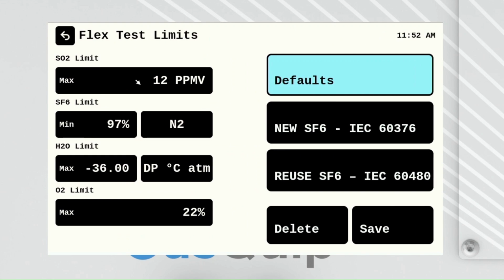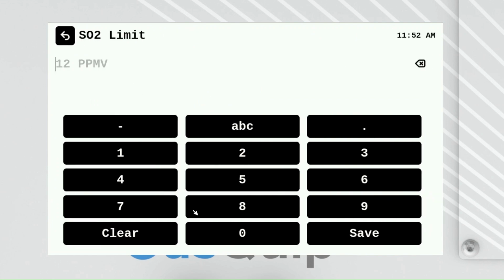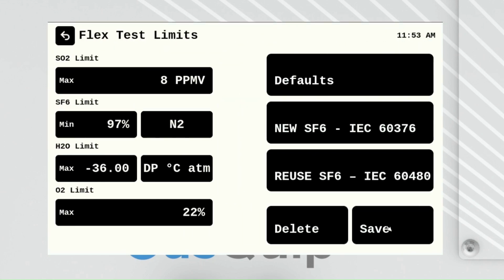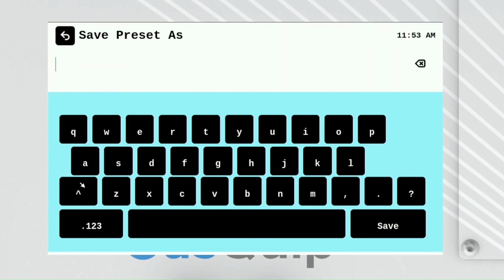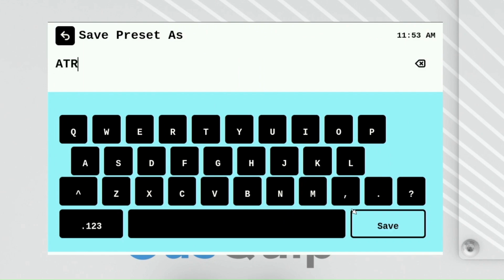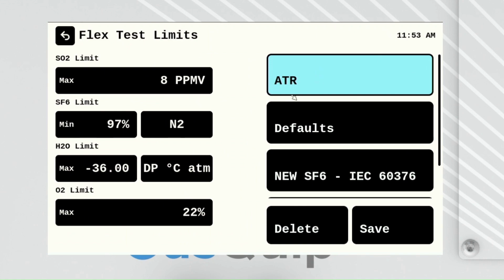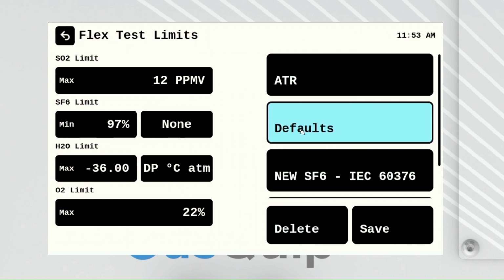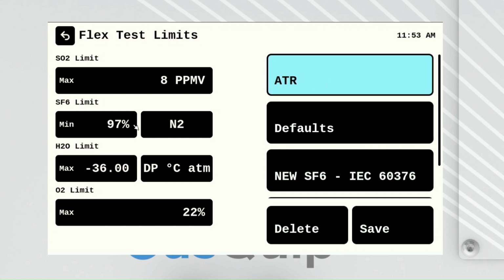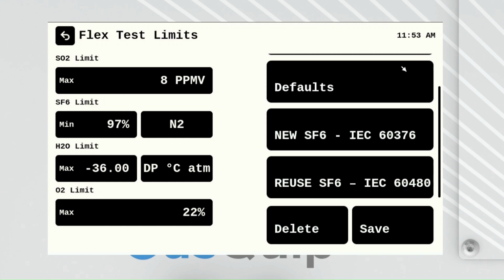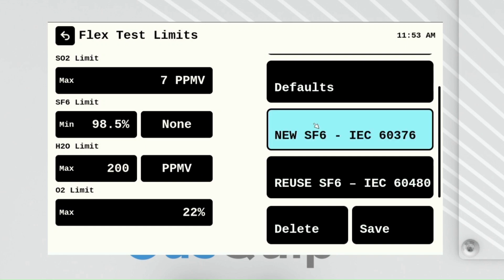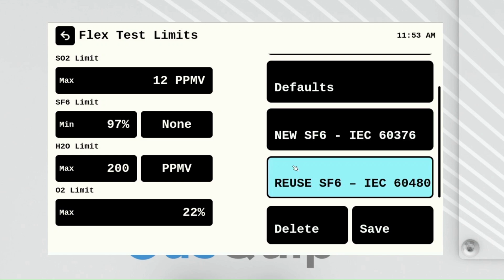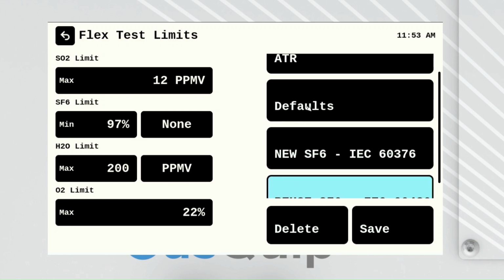So say our internal policy is that nothing can be below or above 8 ppmv on SO2. We can then save that new preset for whatever we'd like. Save it. So now we have a new saved value test limit that's different than what we have as our default values. We have some preloaded values here for new SF6 based on the IEC rating for that, and then also the reuse SF6, which actually corresponds to our defaulted values as well.